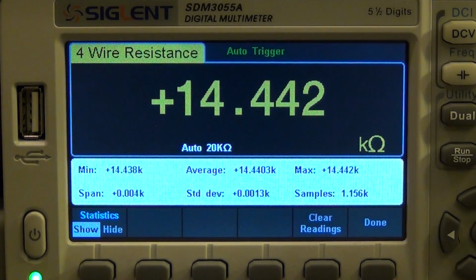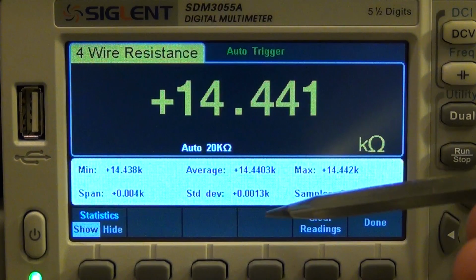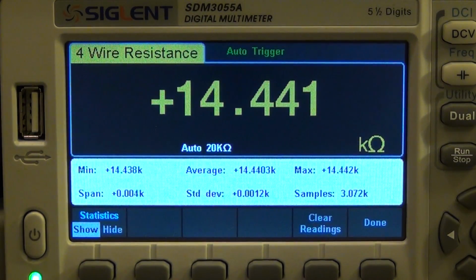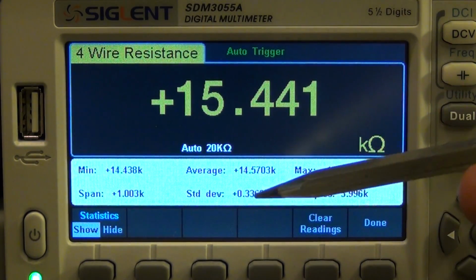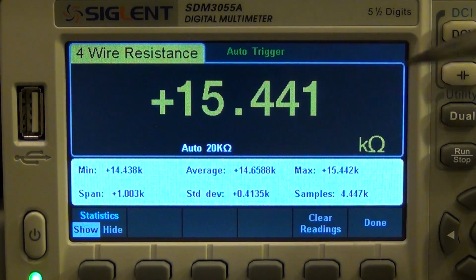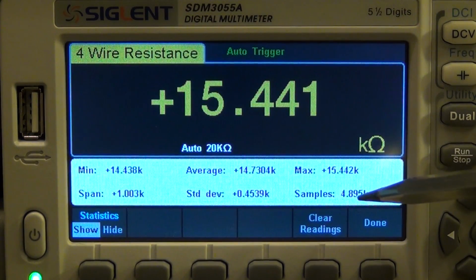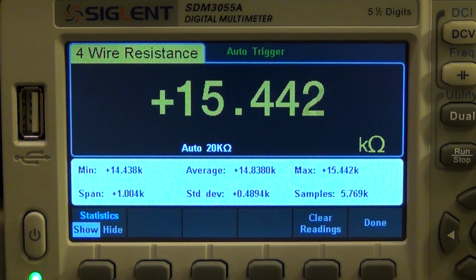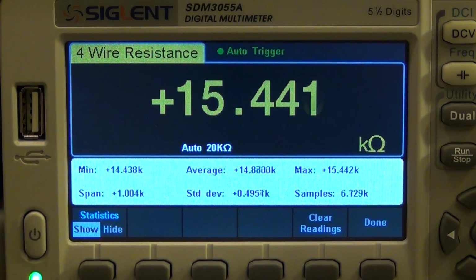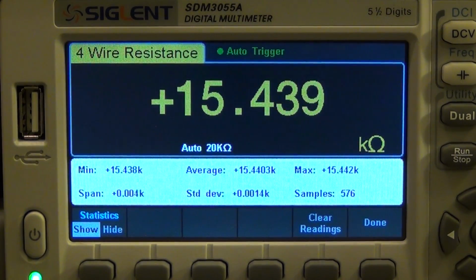Right now I'm on a basic measurement display mode, so I've been measuring a 14.4 kilo ohm resistor, so you can see, for example, the standard deviation is really small, the span is quite small, and as soon as I add a kilo ohm to it, now you can see my span has changed, and the standard deviation is going to grow as the total amount of samples is growing. You can see there's 4.8 kilo samples, and it is rapidly rising. So it is making quick measurements in the background, and it's displaying and updating the statistics menu, which can be quite nice. And if I go ahead and clear it, it will start from scratch.